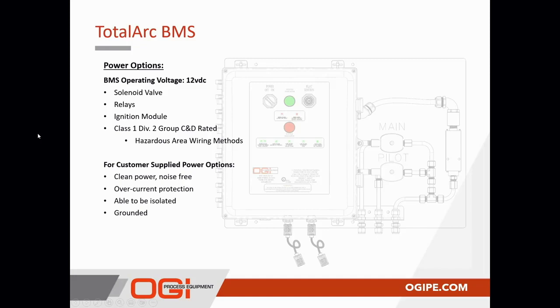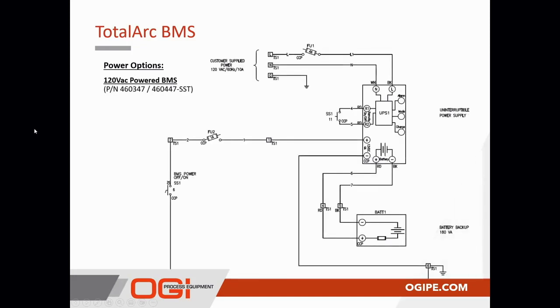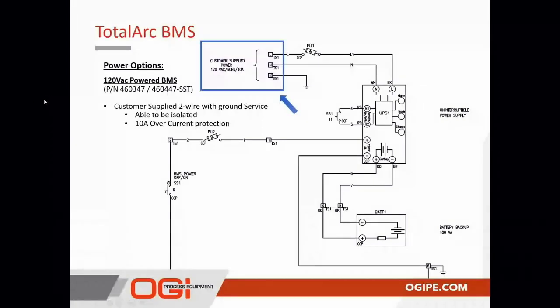So first I'd like to dig into the 120 volt BMS option. Again, all AC to DC power conversion equipment is housed within the BMS panel. For the 120 volt version, the client will be required to supply a 2-wire with ground service. In this case, 120 volts AC, 60 hertz, with 10 amps overcurrent protection. In other words, we'll need at least 10 amps available to the unit to allow it to operate properly.